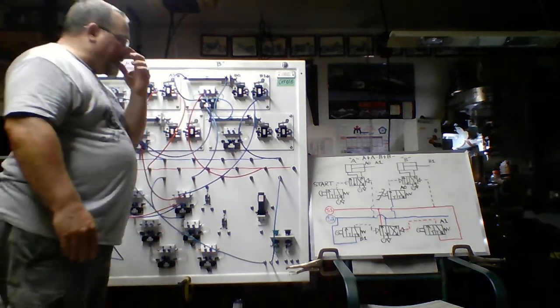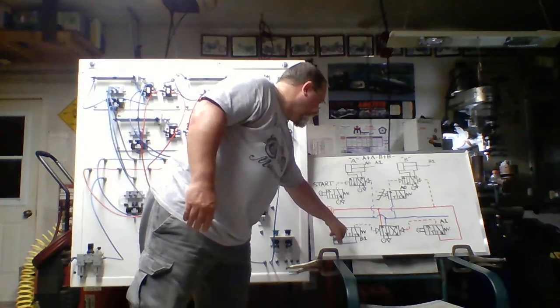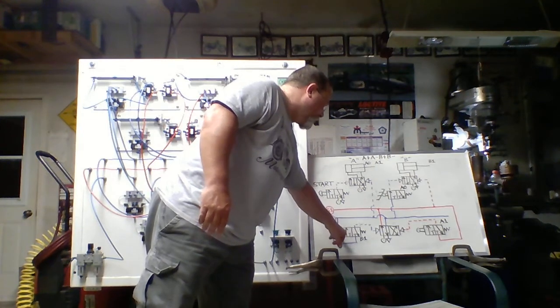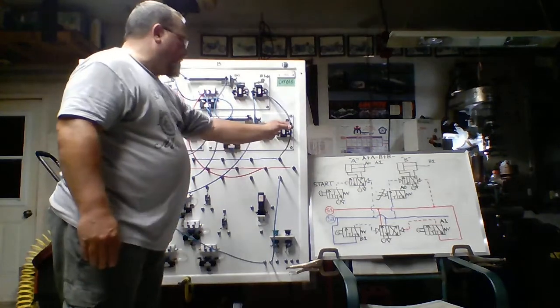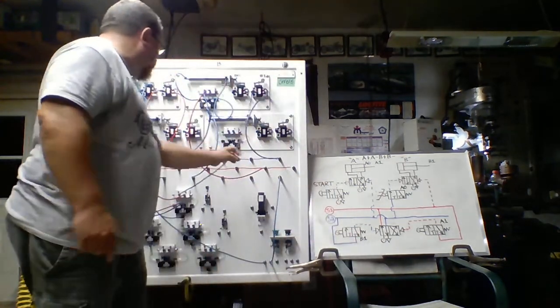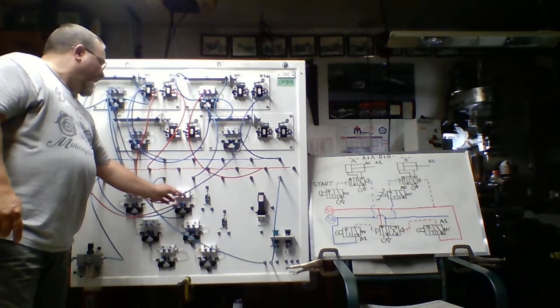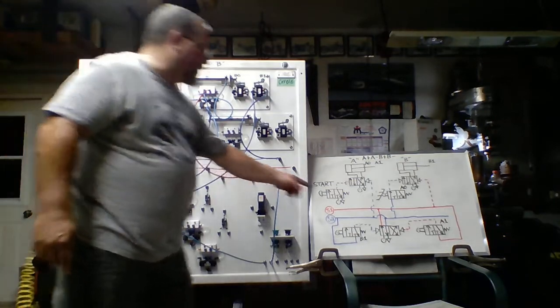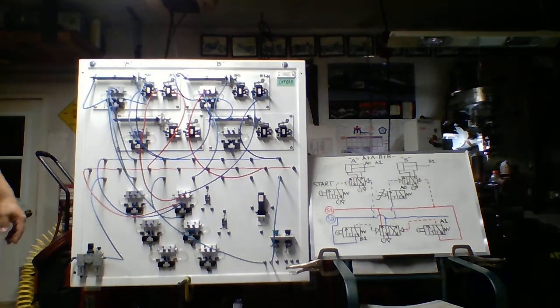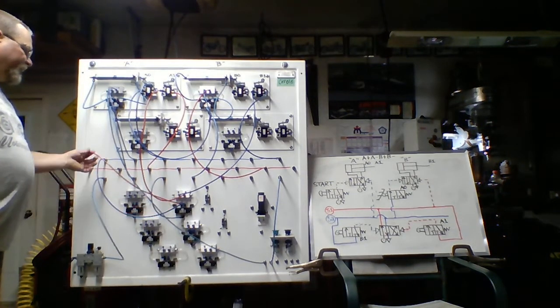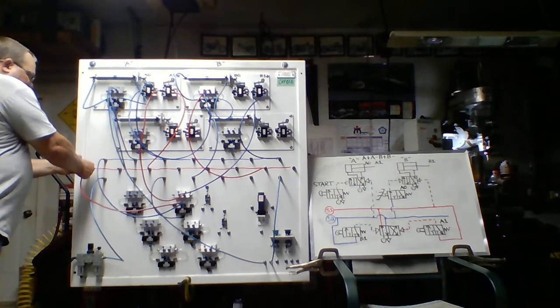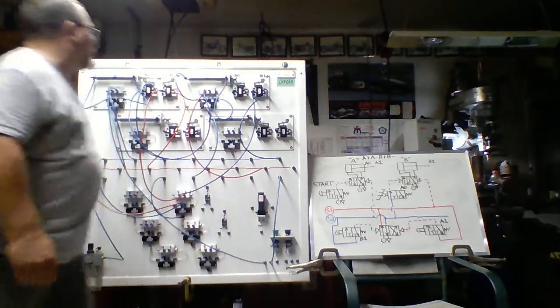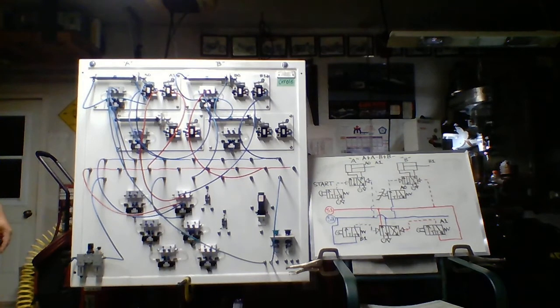At this point in time, when B extends, it gets on B1, which is identified here on the bottom left. Remember, there's energy at source 2 here, and we're going to utilize that energy. So we plumb that into B1. So we look at B1. We're coming off source 2, as indicated. We come out of B1. Here's my pilot line going over to my cascade valve. And, of course, what's happening here is we shift the cascade valve, as shown. It brings it back into its home position, or original position, which means, of course, we'll have energy at source 1. So this is source 1 here coming out of my cascade valve. As you can see, there's energy there. And when we push the button, there you have it. Thank you.